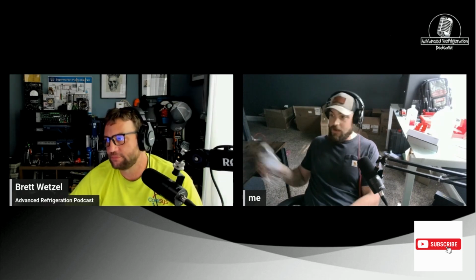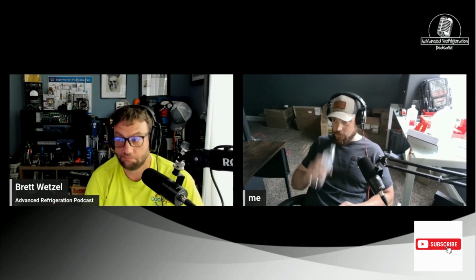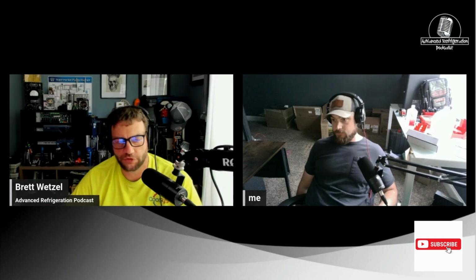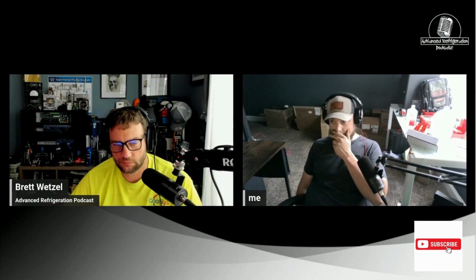So hot gas ball valves, generally those are a pain. Depending on how it is, you may have to pump the whole rack down. We've had some where we've gone to do hot gas ball valves and we can't get the header down because when you drop the header pressure, it's bleeding back through the solenoids. And there's no ball valves before the solenoids? No, the ball valves are at the solenoids for the hot gas headers. You got ball valve, then solenoid, then it dumps into the circuit. Oh, I see what you're saying, so you basically would have to pump down the whole damn thing.